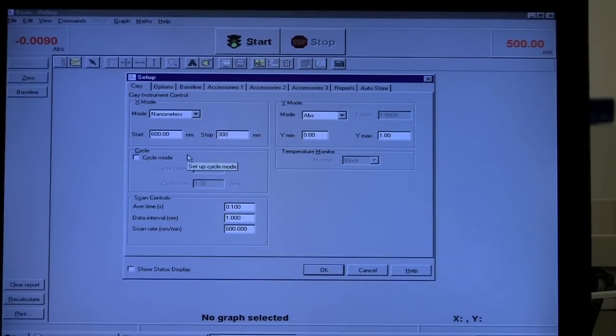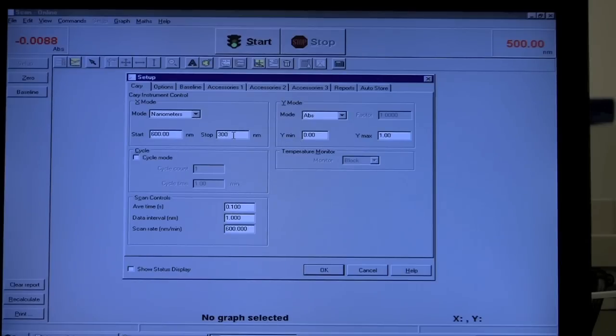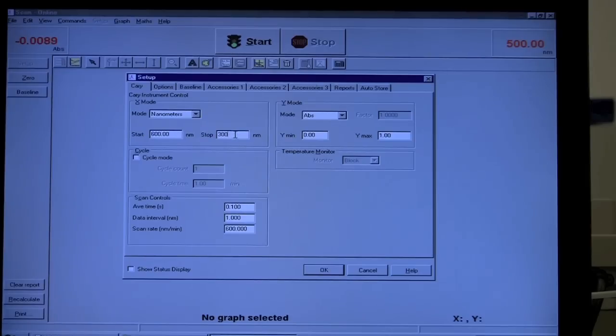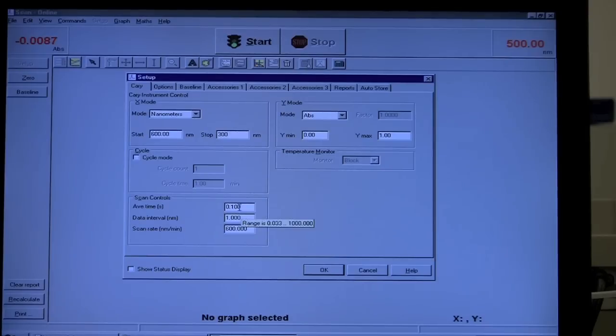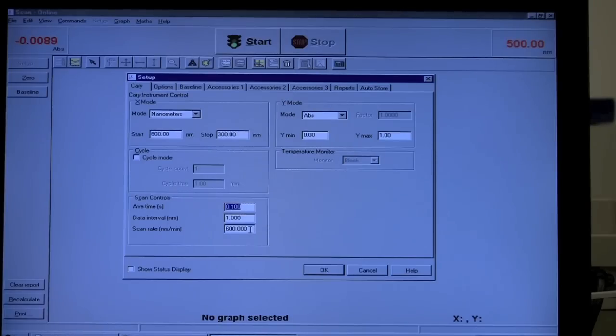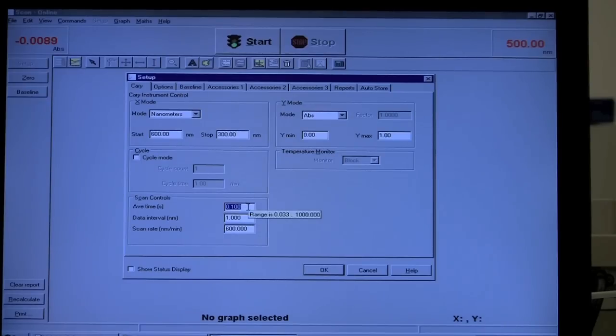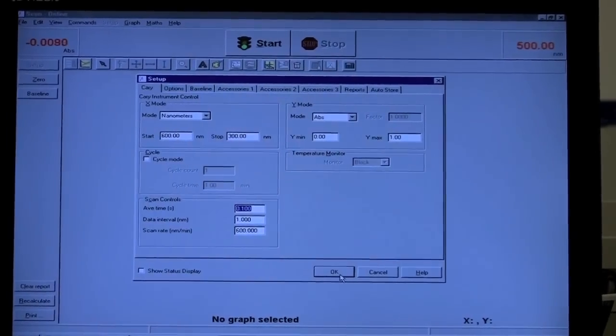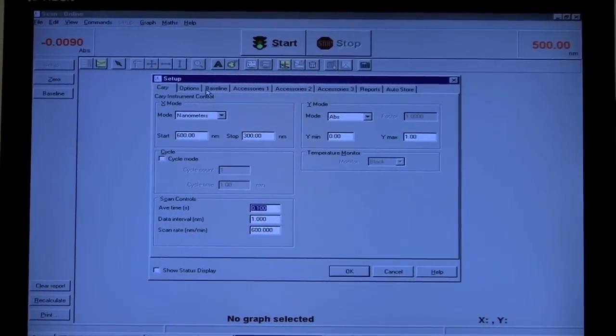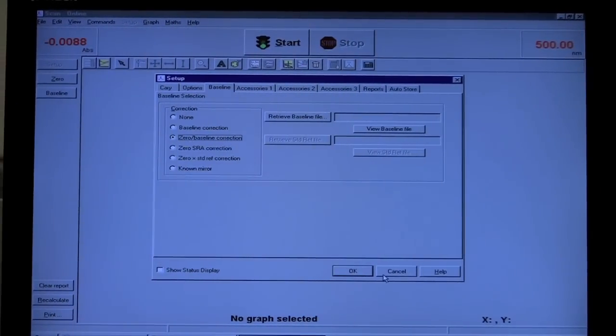Be aware that to go to the ultraviolet, you will need quartz cuvettes. Glass and plastic cuvettes will absorb in the ultraviolet and you'll just not see any spectrum at that point. So set the limits here. If you want to scan more quickly, you can adjust either the averaging time or the data interval. The defaults here should be reasonable, but you may want to adjust these if you know why you have a reason to. For example, you could scan at larger intervals or average for longer or shorter times. We'll just leave it with the defaults here.